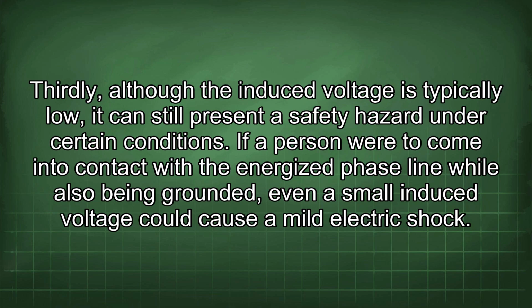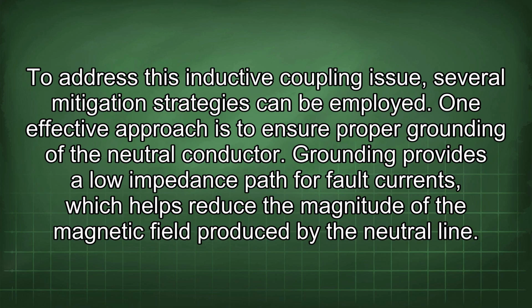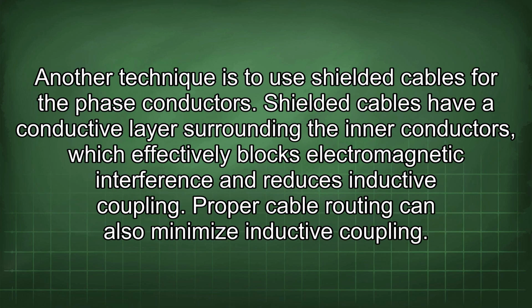If a person were to come into contact with the energized phase line while also being grounded, even a small induced voltage could cause a mild electric shock. To address this inductive coupling issue, several mitigation strategies can be employed. One effective approach is to ensure proper grounding of the neutral conductor. Grounding provides a low impedance path for fault currents, which helps reduce the magnitude of the magnetic field produced by the neutral line. Another technique is to use shielded cables for the phase conductors.